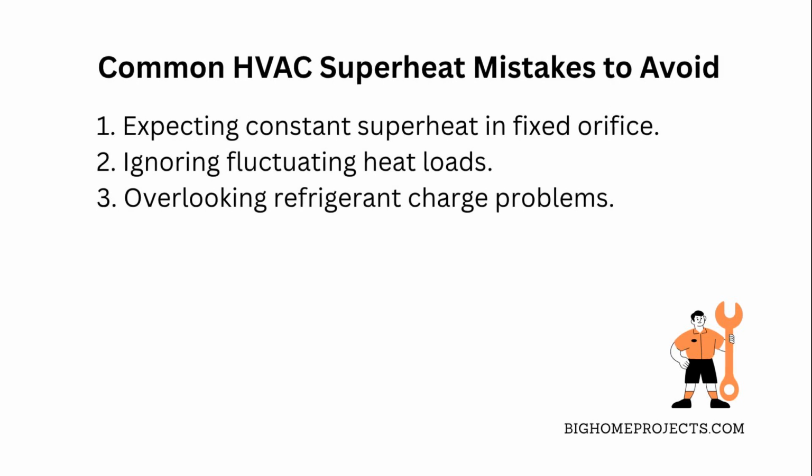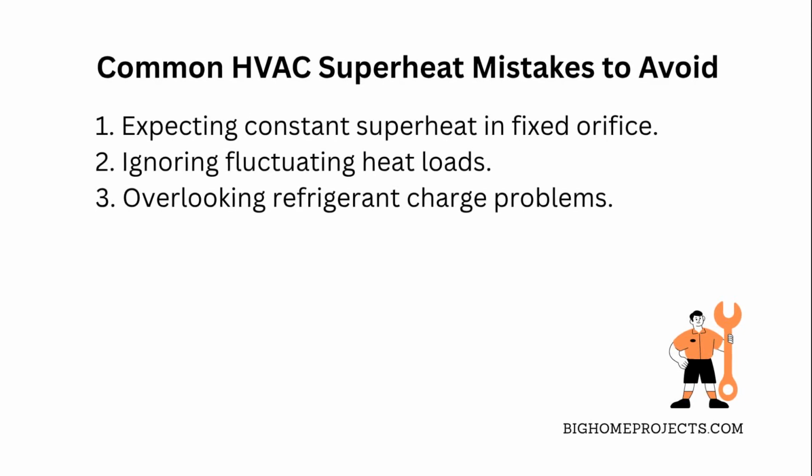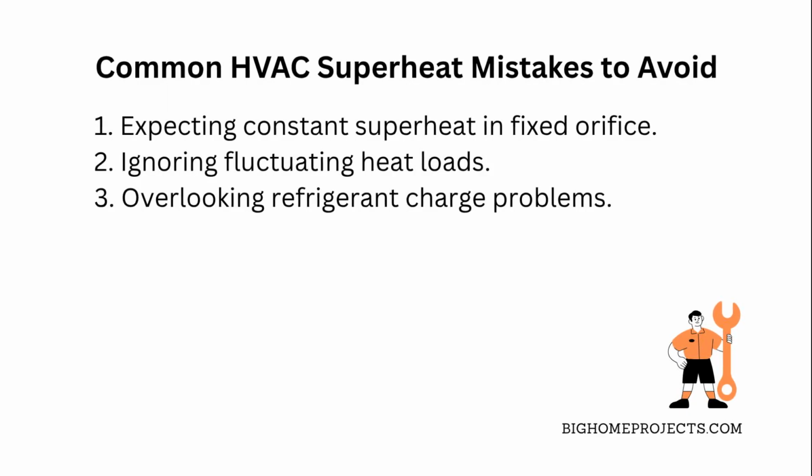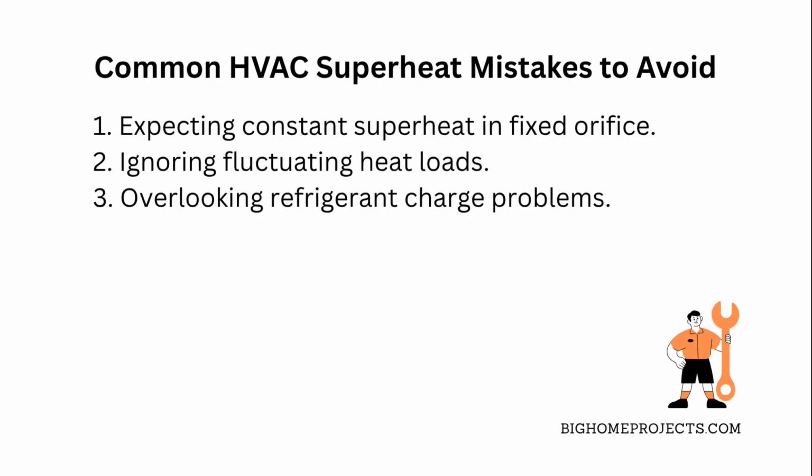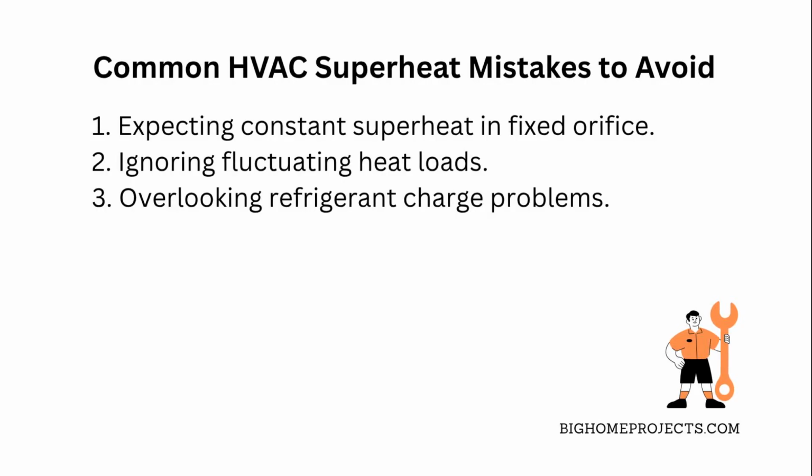Another common issue is ignoring fluctuating heat loads. If you only check superheat when the system is running light or heavy, you won't get the full story. Last but not least, failing to check for refrigerant charge problems can throw off your readings big time. Always confirm the charge first before chasing other issues.